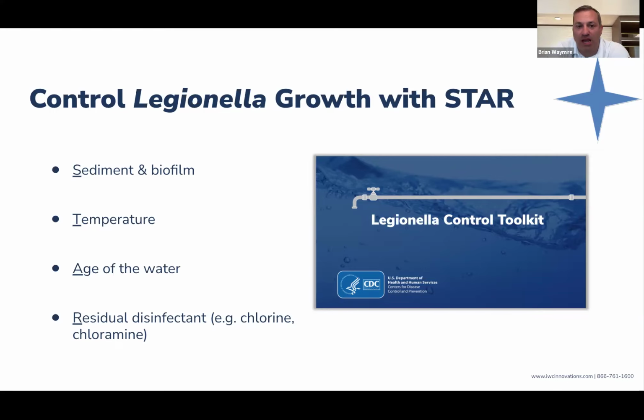ASHRAE 188 and those water management documents are solving for this. This comes straight out of the CDC: sediment and biofilm, temperature, age of water, and residual disinfectant. We call it the STAR acronym. All four of these are interrelated, meaning if you control one but not the others, those other three will get out of control and cause you issues. So remember, all four are interrelated.